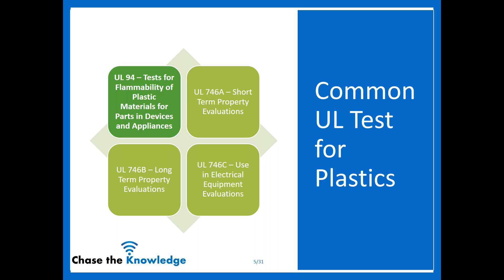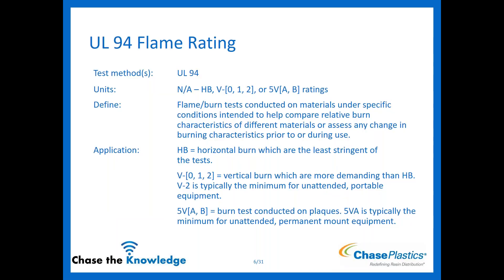Starting with UL 94 for flame. UL 94 addresses the flammability of the material itself. There are a handful of different ratings under this test. You've got your HB, which is horizontal burn. You have your vertical burns — V0, V1, and V2. And then you have your 5Vs — 5VA and 5VB. Your 94 flame rating: the flame and burn test is conducted on these materials, and the conditions are used to compare the relative burn characteristics of different materials to see how they're going to perform in use.